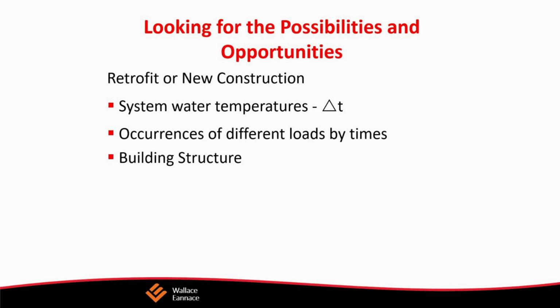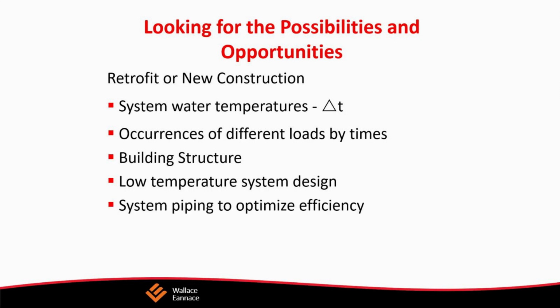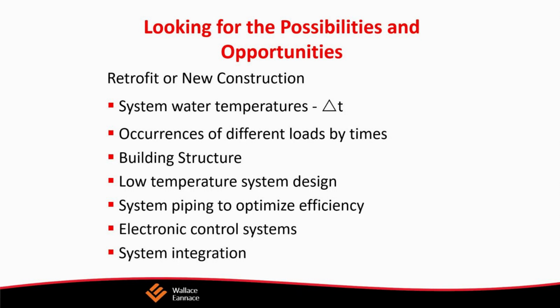So when is it time to retrofit a system? Well, we can say when the heating boilers fail, with the age of the equipment, when the boilers wear out, when maintenance costs are constantly increasing, and if we're just looking to save money on fuel and increase our energy efficiency, we might want to switch from oil to gas or from electric to gas, or we may desire a dual fuel system, depending upon the price of various fuels. And how should that retrofit take place? Well, only by fact-finding and investigating the entire system, not just looking at the BTU capacity of the boiler, but really considering the entire heating system of the particular building.